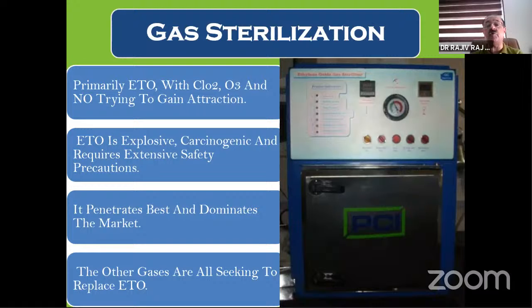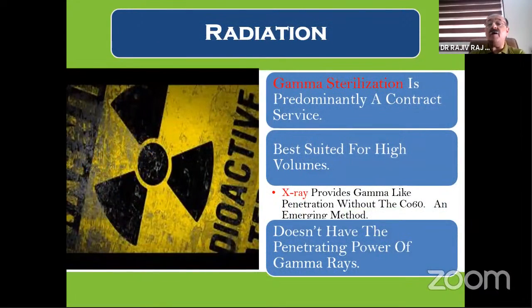Gas sterilization. So from heat we come to gas. And today the most popular one is the ETO. And that is the reason basically is the cost factor. But it is explosive and carcinogenic and requires extensive safety precautions. It penetrates best and is very, very commonly used today. Gamma irradiation or gamma sterilization is best suited for very high volumes, and usually hospitals of most sizes would not be using gamma ray irradiation.